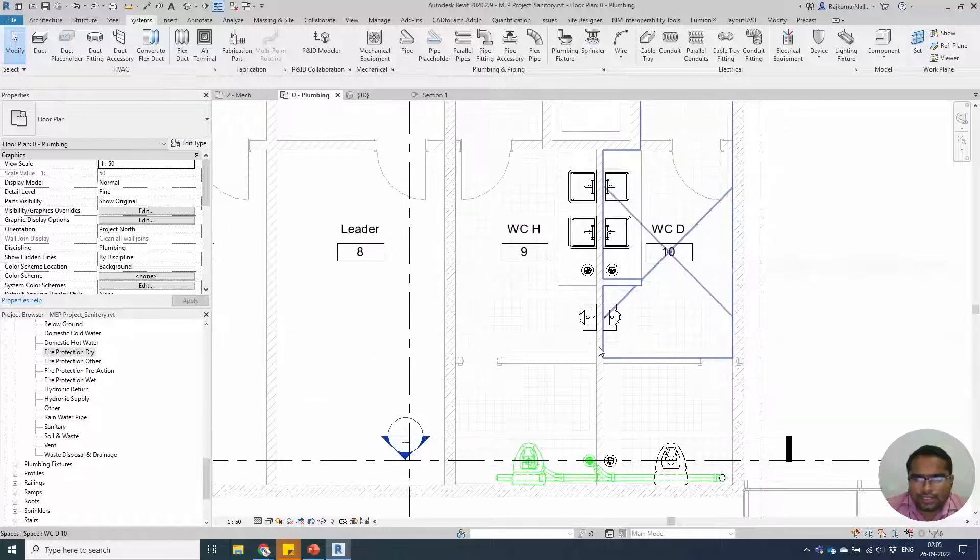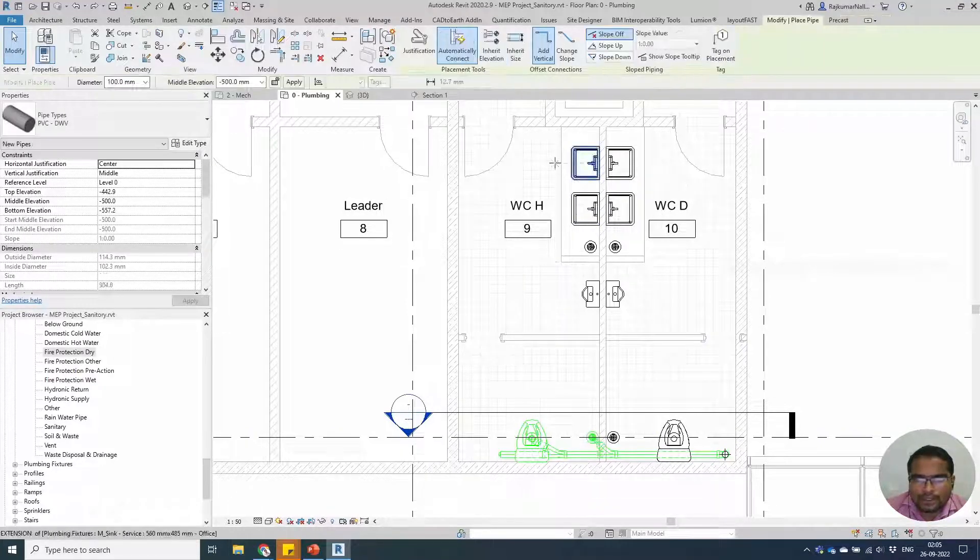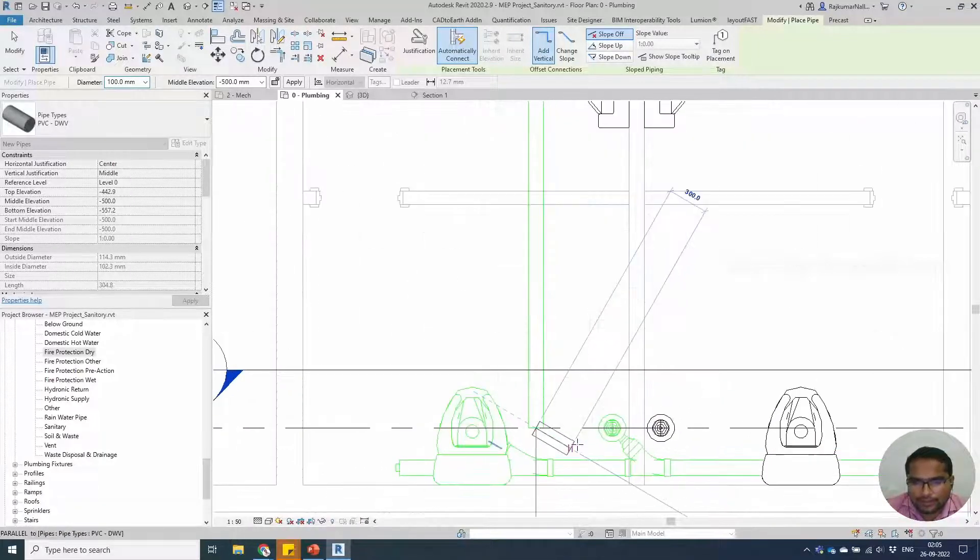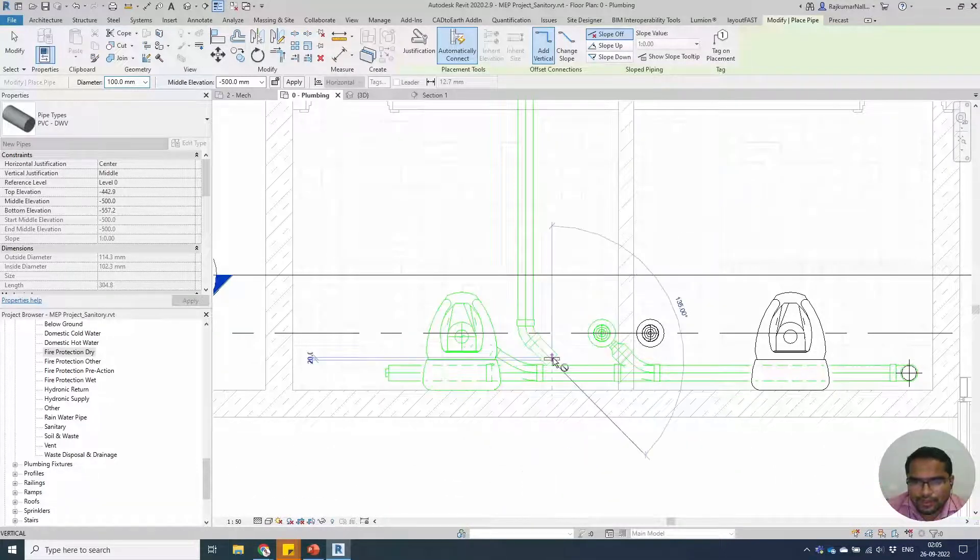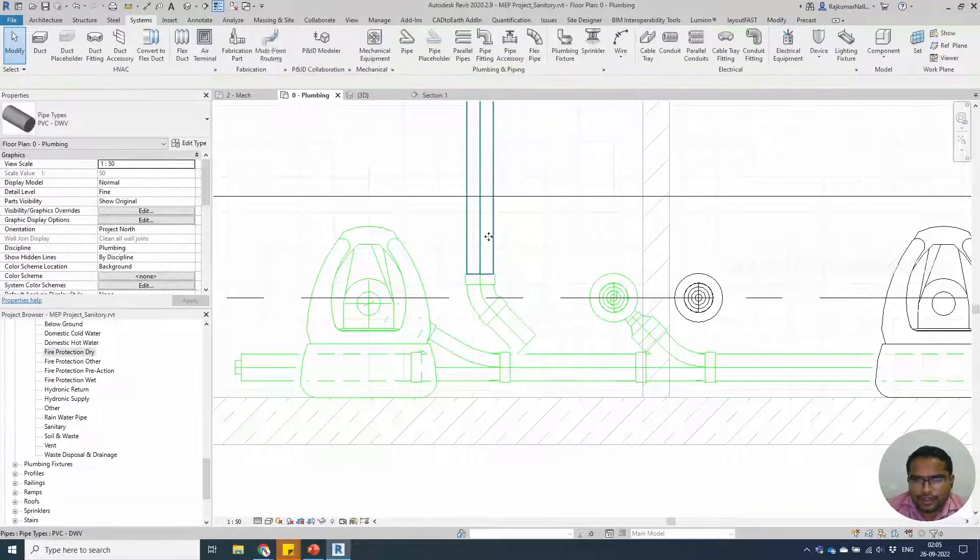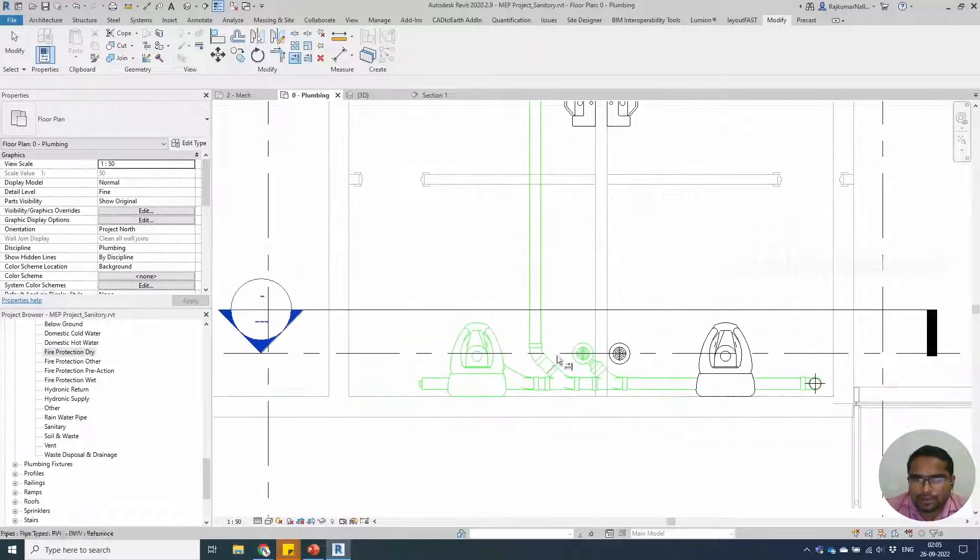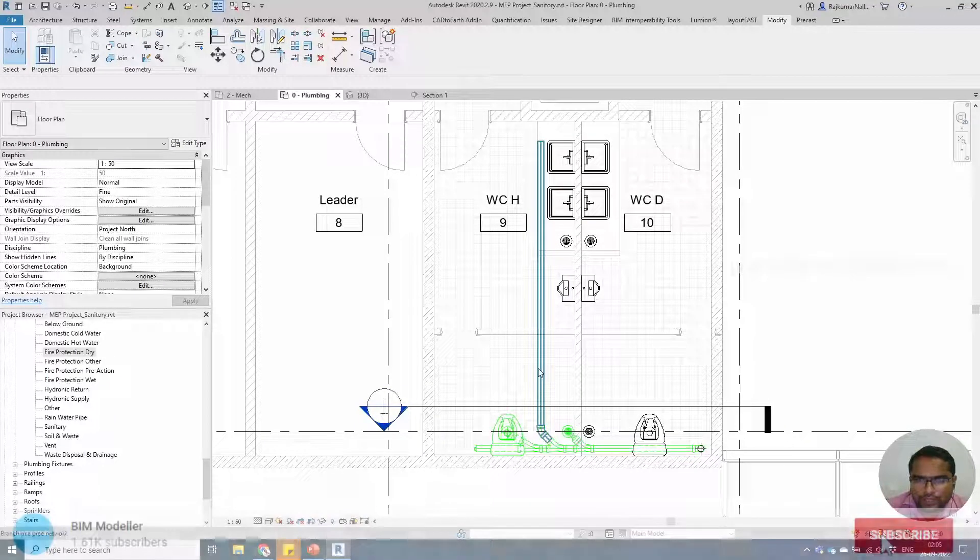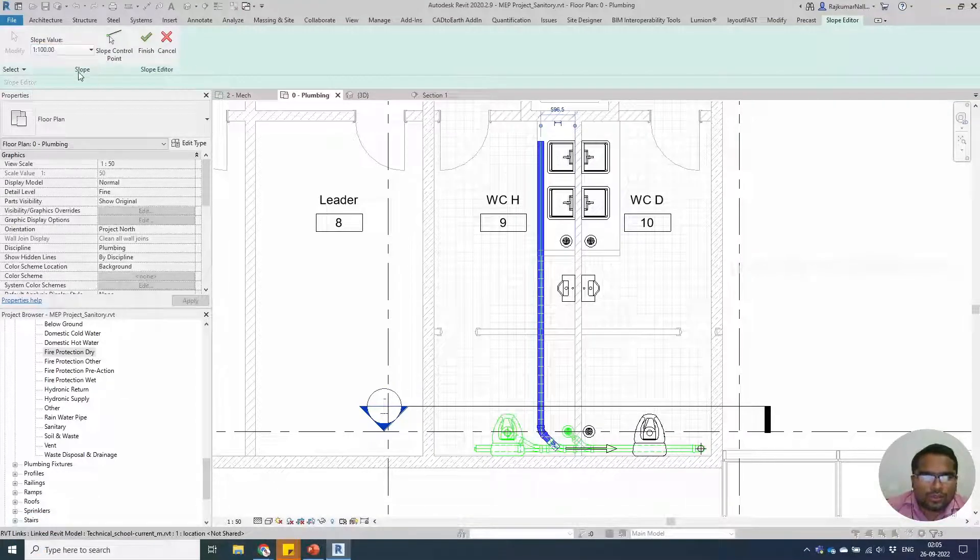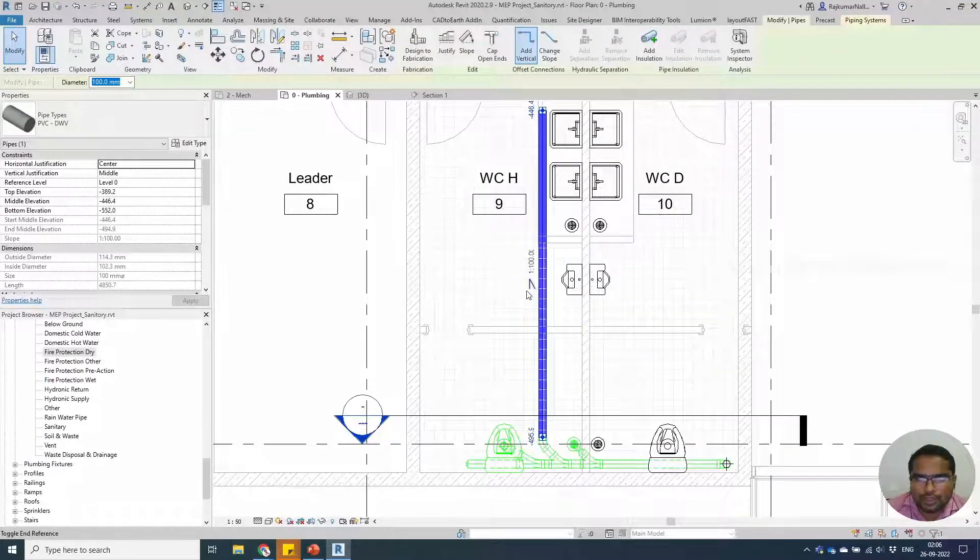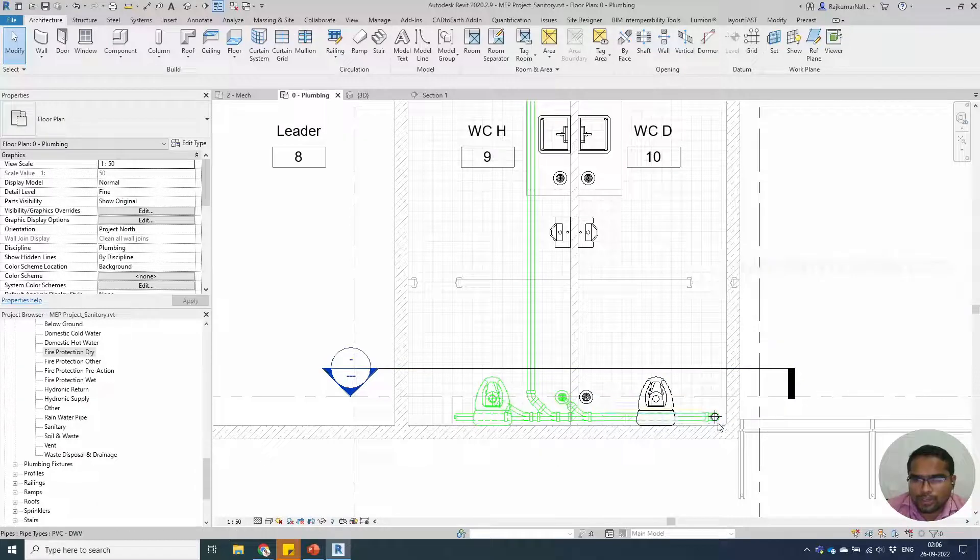Once you have done this connection, we will be able to go to the other side and create the pipe at minus 500 from this place to this end. Use the trim and extend command, connect the pipe. If you are trying to apply a slope value, you can apply a gravitational pipe slope 1 is to 100. If you select the pipe, you will see that the pipe is running at 1 is to 100 slope.